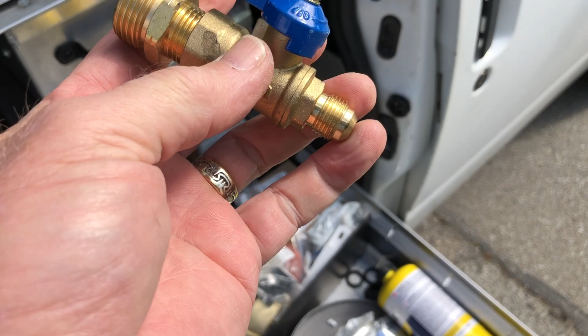I'll get on roofs sometimes that have water spigots for swamp coolers, and I'll flare a piece of pipe here to a compression 3/8, and I can bush it down to 1/4 so I can get my garden hose, and then I can wash coils out on a roof. So I'll tap this into the HVAC cooler water line so I can hook up my garden hose on the roof.